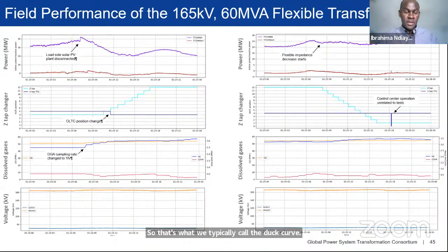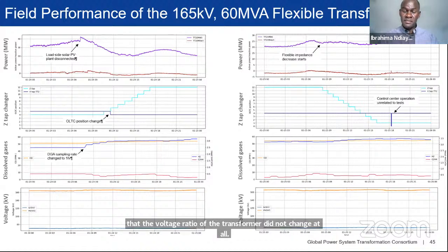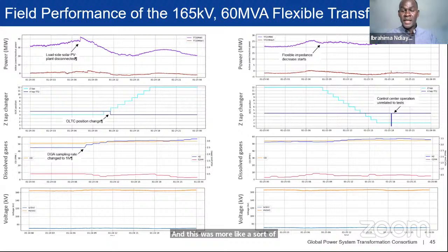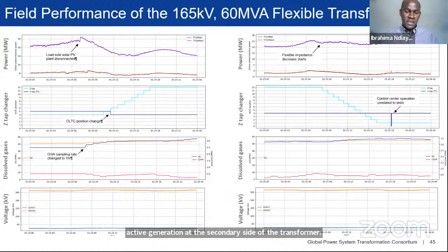Importantly, you can also notice at the bottom curve that the voltage ratio of the transformer did not change at all. This was a slightly radial system, so there was no active generation at the secondary side of the transformer. There was only active generation at the primary side. So we were not trying to do anything to maintain that voltage ratio. So this was really giving the confidence that the flexible transformer, as a power flow controller, is working and operating as expected.